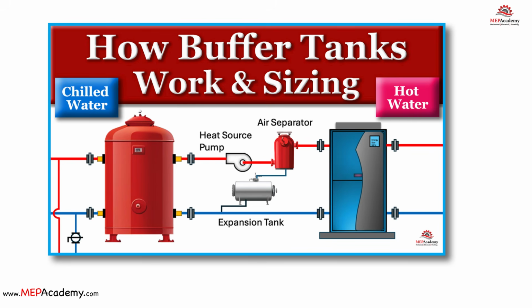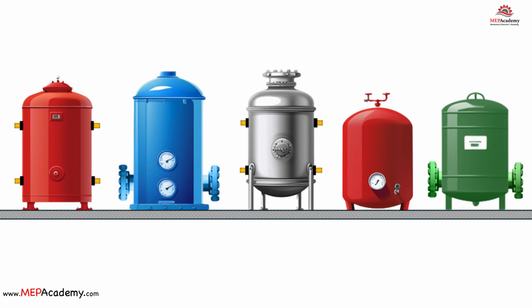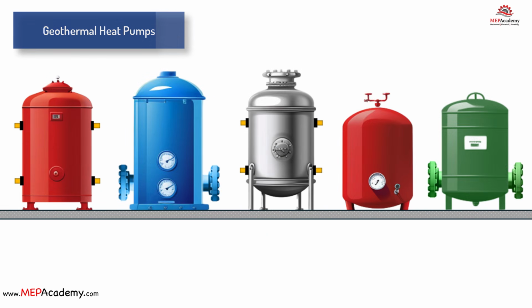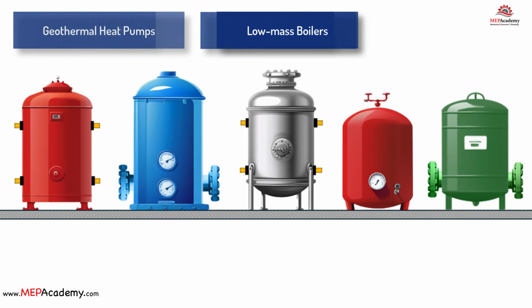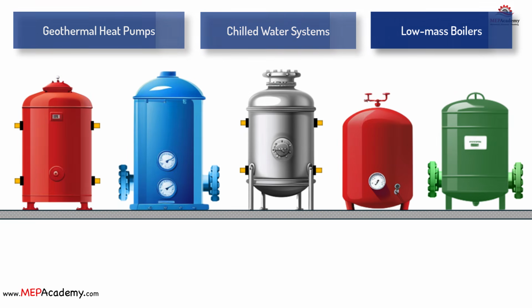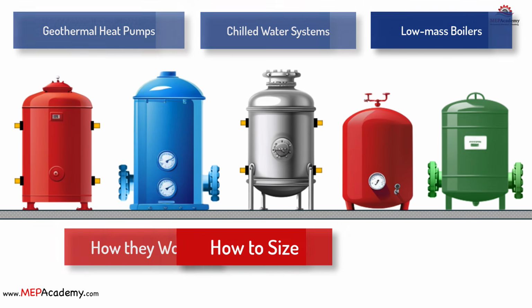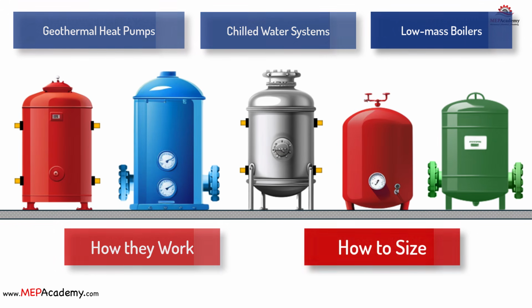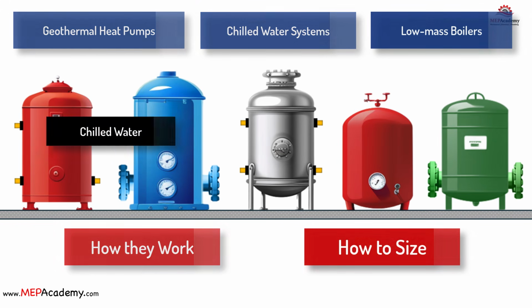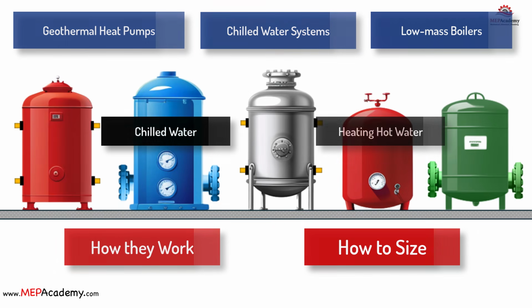A buffer tank acts as a thermal energy battery for heating hot water or chilled water systems that lack enough water volume during load conditions to avoid short cycling. They can be used with geothermal heat pumps, chilled water systems, low mass boilers, and low mass radiation systems. We'll show you how they work and how to calculate the size of two buffer tanks, one for a chilled water system and the other heating hot water.